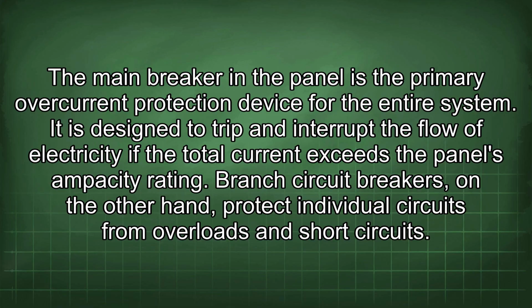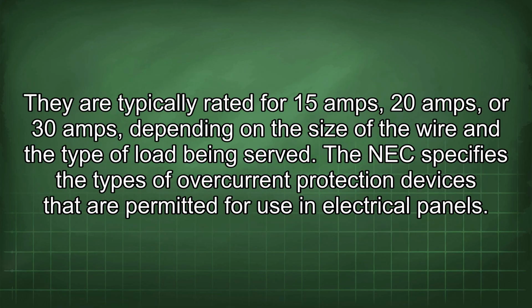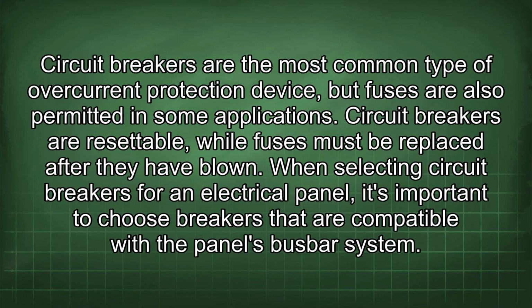Branch circuit breakers, on the other hand, protect individual circuits from overloads and short circuits. They are typically rated for 15 amps, 20 amps, or 30 amps, depending on the size of the wire and the type of load being served. The NEC specifies the types of overcurrent protection devices that are permitted for use in electrical panels. Circuit breakers are the most common type of overcurrent protection device, but fuses are also permitted in some applications. Circuit breakers are resettable, while fuses must be replaced after they have blown.